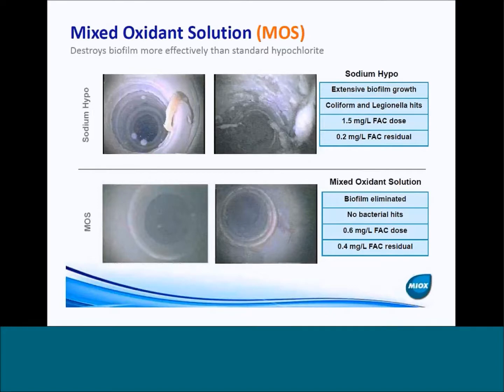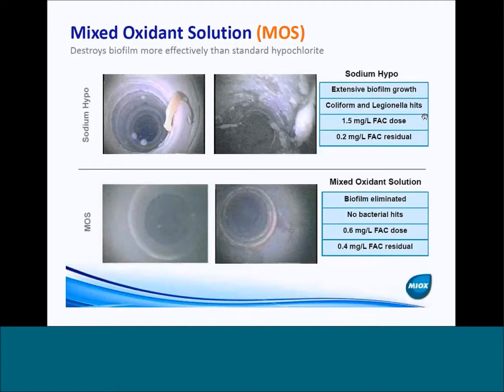From that superior disinfection efficacy, in almost every installation where we know there's a biofilm problem, we've seen that mixed oxidant solution destroys biofilm more effectively than standard hypochlorite. This is one example from borescope images — actually from a hot springs in Japan where they implemented one of our systems. Before, they were using sodium hypochlorite and had a lot of biofilm growth. You can see the mass of biofilm and coating going down the pipe. They had positive coliform and legionella hits, and they approached us because they had had a fatality resulting from a case of legionellosis.